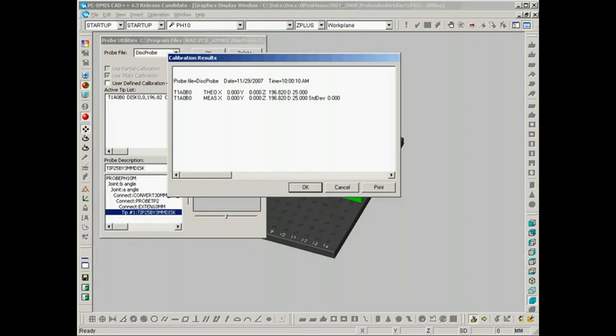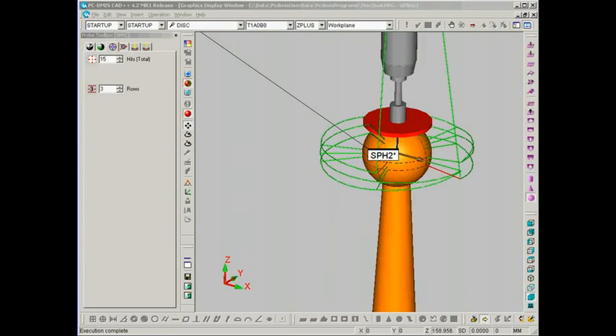If it's not, then try reducing the probing angle from ±7.5 degrees down to, say, ±5 degrees. And we would do that for thinner discs. Or you could increase the probing angle from ±7 degrees up to ±10 degrees for thicker discs. So you need to review these results carefully. This is what it looks like when the disc probe is calibrating at the ±7.5 degrees. You'll notice that we don't take any hits on top of the calibration artifact.